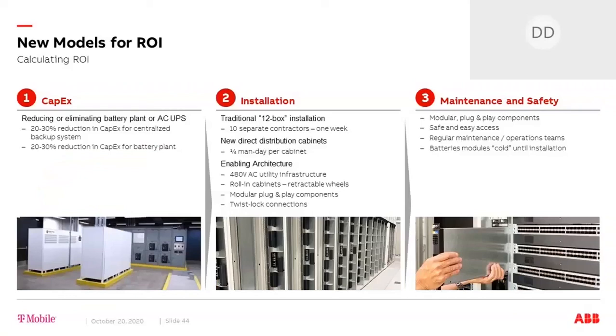Essentially, we have reallocated the UPS or battery plant and electrical switchgear capital to add a generator and a utility instead. All future UPS and or battery project and battery plant capacity upgrade projects are eliminated. In our samples, we saved about 20% CapEx if we only compared the initial electrical systems costs.